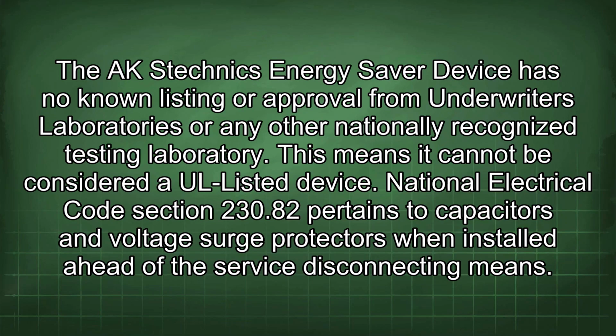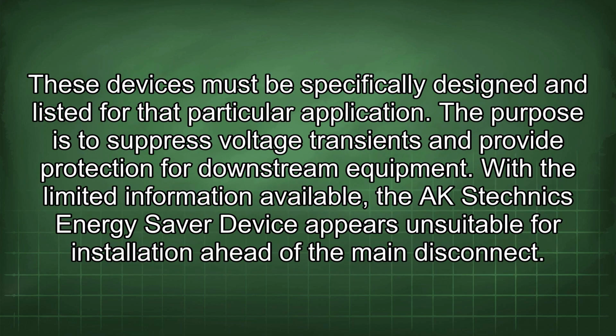The AK Stechnics Energy Saver device has no known listing or approval from Underwriters Laboratories or any other nationally recognized testing laboratory. This means it cannot be considered a UL-listed device. National Electrical Code Section 230.82 pertains to capacitors and voltage surge protectors when installed ahead of the service disconnecting means. These devices must be specifically designed and listed for that particular application.